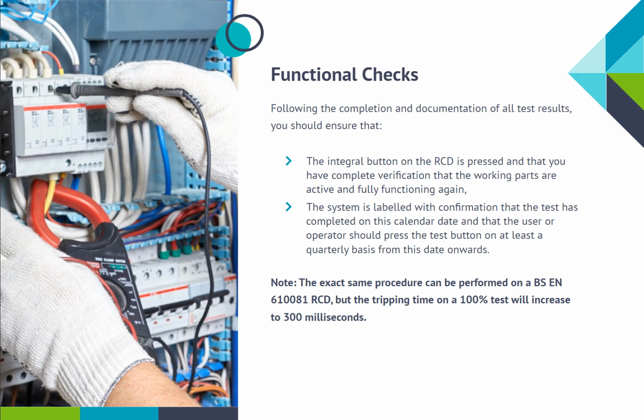Note: the exact same procedure can be performed on a BS EN 61008-1 RCD, but the tripping time on a 100% test will increase to 300 milliseconds.